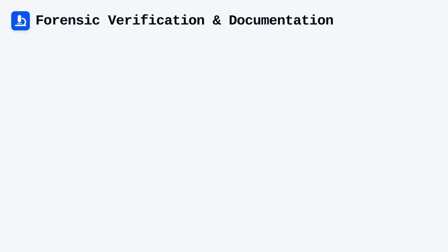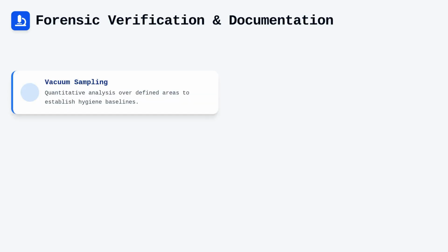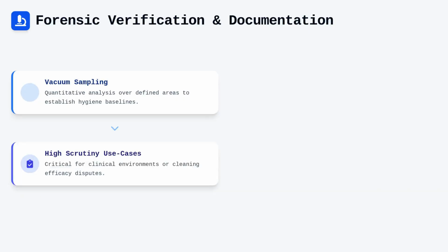Beyond visual metrics and surface testing, forensic verification can involve vacuum sampling if the situation calls for a higher level of scrutiny. Vacuum collection entails taking a surface sample over a defined area and analyzing the collected material, which allows you to establish a quantitative baseline for the system's hygiene. This method is particularly useful in environments where clinical cleanliness is required or when there is a dispute regarding the efficacy of the previous cleaning efforts.